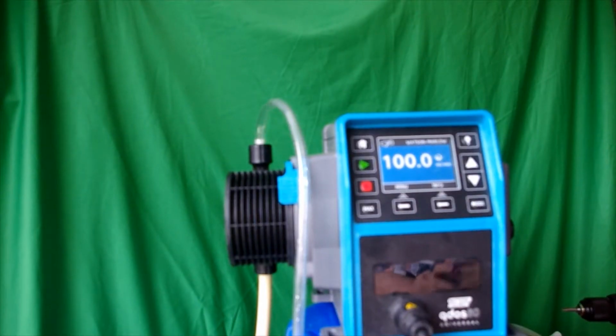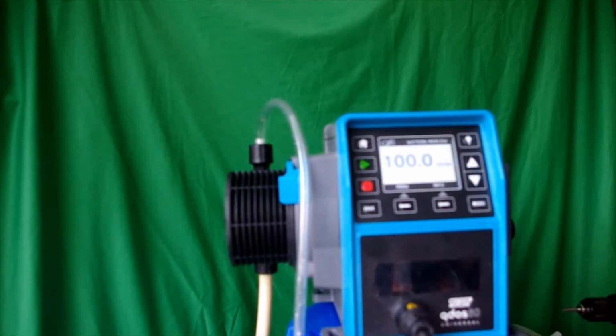So I had a customer ask me about wiring up an alarm on a qdos pump. This is a qdos 60 universal. It comes standard with 2 alarms. So in this particular case, the customer wanted to wire it up to a leak detector so that if the head fails, then the pump would let the SCADA system, DCS, control operator know that the pump has failed. So if you wanted to wire up an alarm, you would stop the pump.